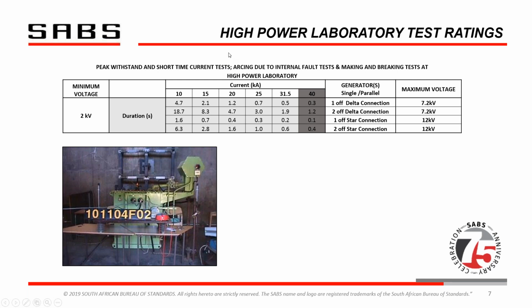I'm not going to go into the full detail of the plant, but basically, the 2 generators supply the fault currents. So you run the generators up, you get them to a certain voltage. The voltage is obviously calculated, and then based on what fault current is required, the operator, or Lucas, Seth, will determine the reactor requirements that need to be put in circuit in order to produce certain fault currents. And you can see here that for the generator connections, you either use 1 generator in delta connection, 2 in delta connection, 1 in star, or 2 in star configuration. There's your maximum voltages. With the 2, you never connect the 2 in series.